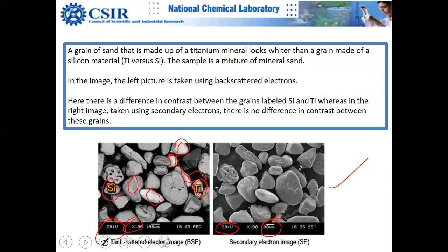Some charging you can see here, because silica and titania are different: titania is a semiconductor, but silicon oxide is a perfect insulator. So you're going to see a lot of charging, but the sample might have been coated and grounded with a carbon tape or something. Underneath there is always a carbon tape. You're bombarding so many electrons, so you have to make sure that you keep these particles neutral.